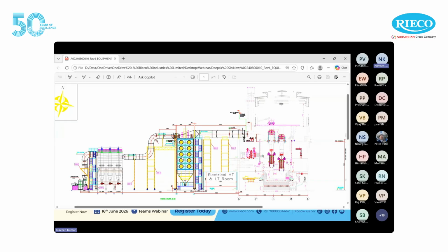It will run all conditions when the temperature is at peak, and it will turn off some of the fans based on the inlet temperature. And there is a dilution damper where, as I said, if there is a shoot-up of the temperature, then this dilution damper will open in proportion to the amount of air required to make sure this outlet temperature can be achieved.